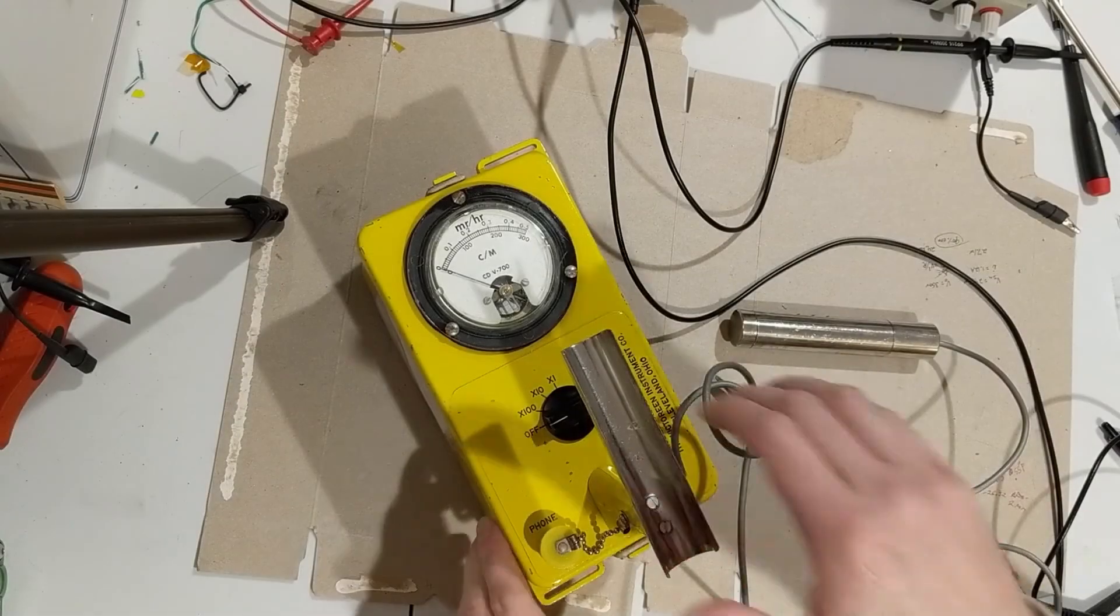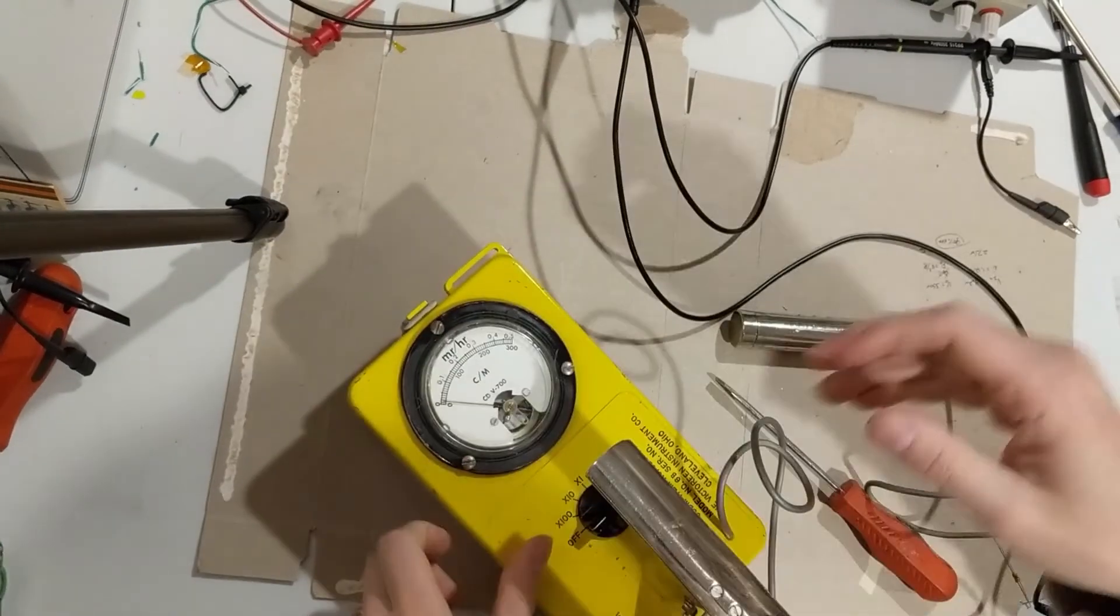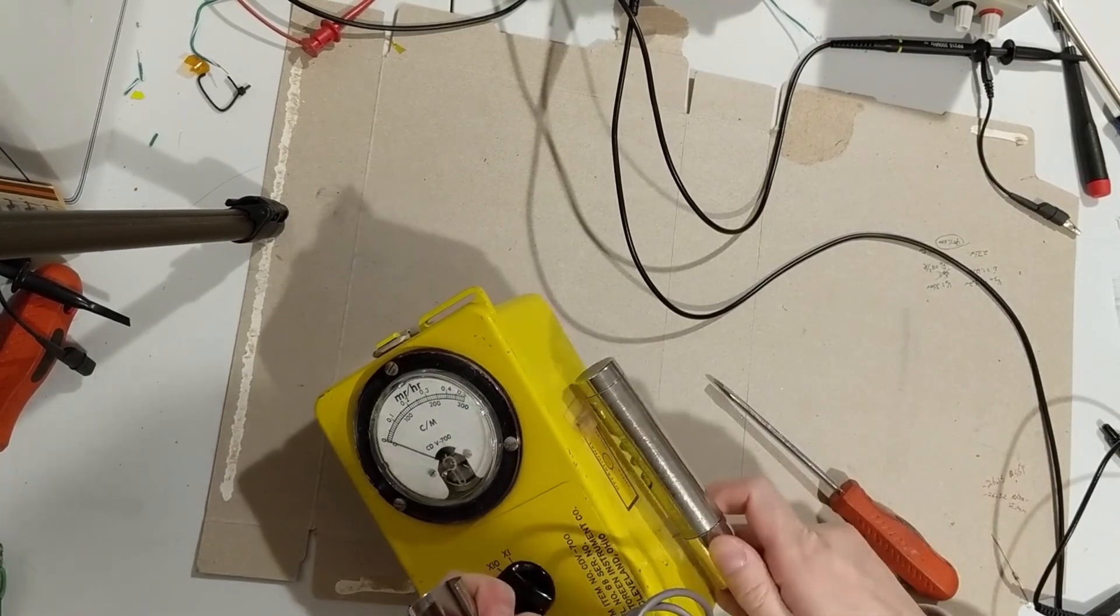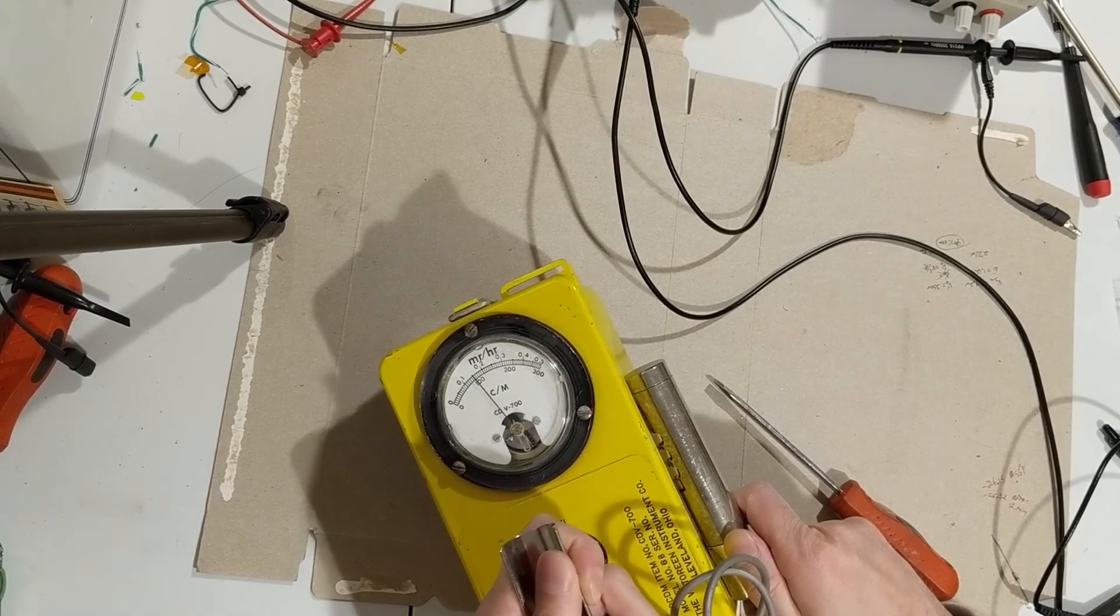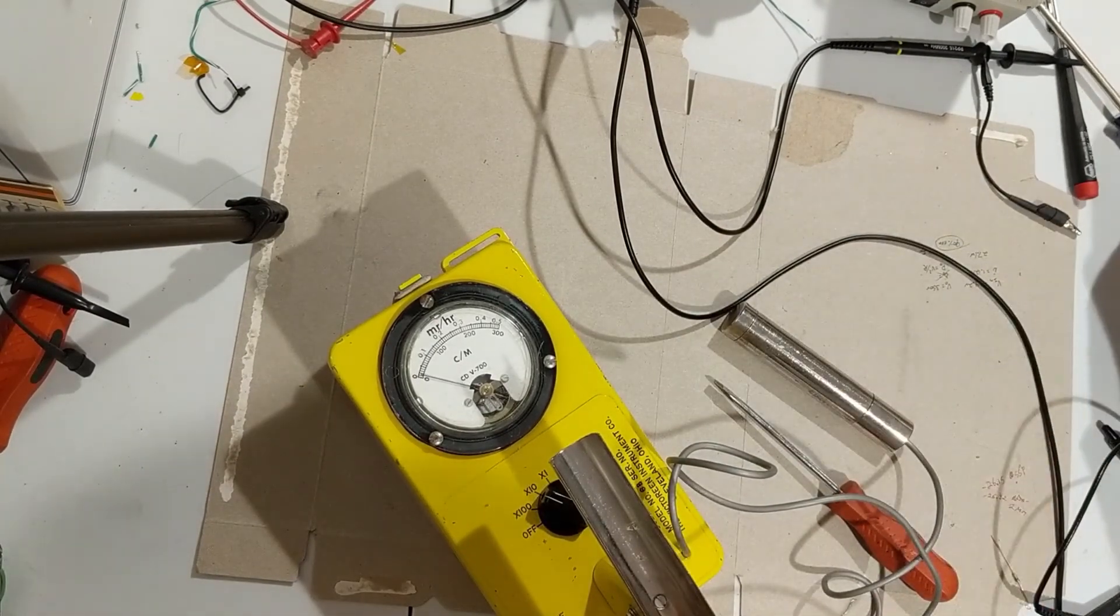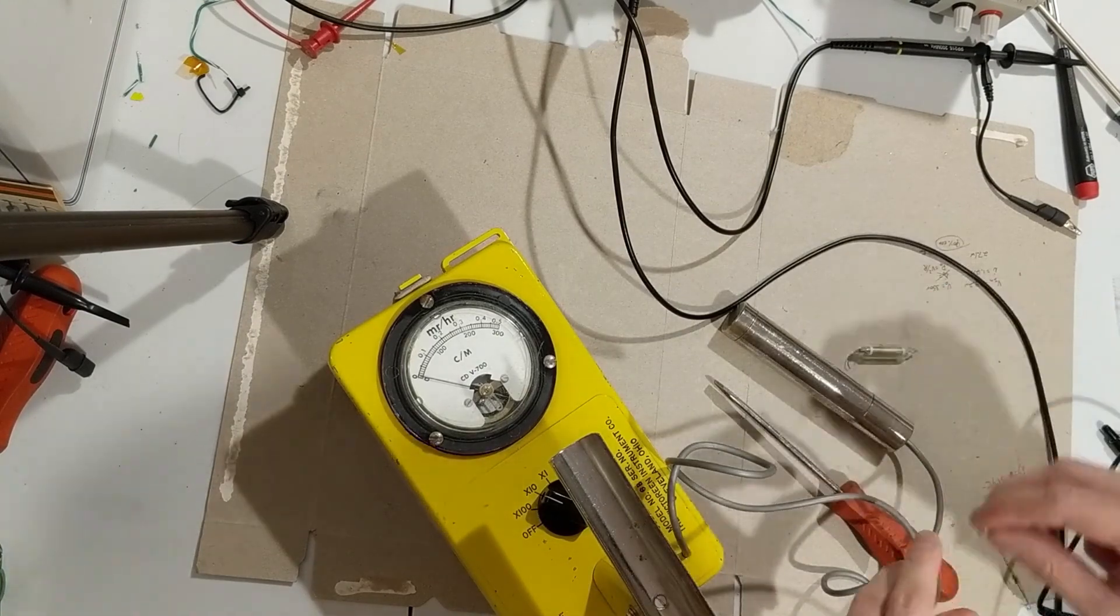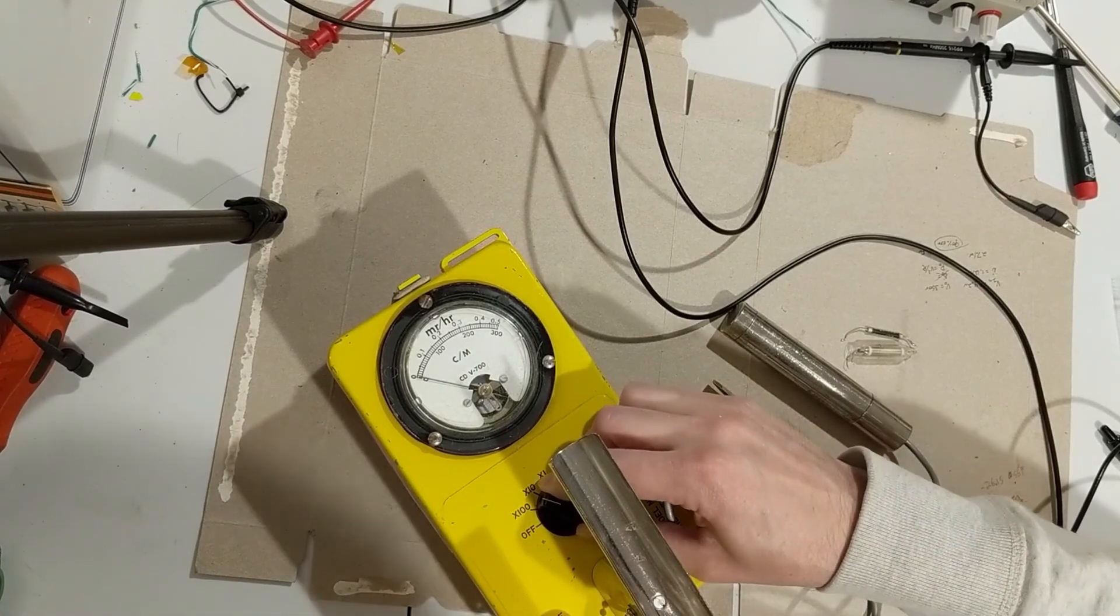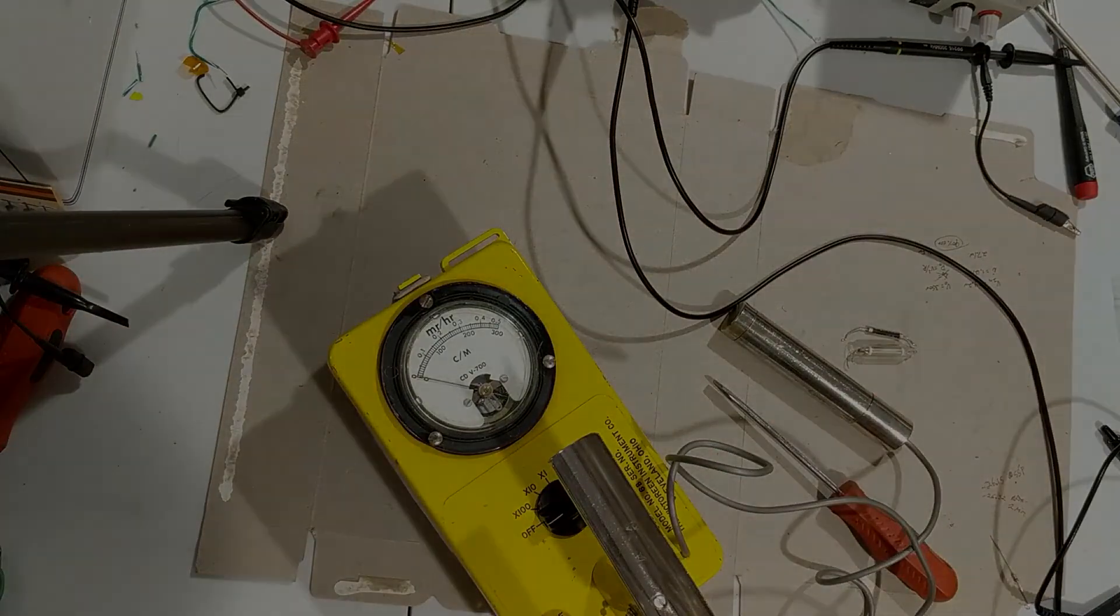So there we go, unit's back together. And we turn it on with this check source and I would expect it to be approximately 0.15 millirem per hour. So everything's good. It's pretty straightforward, the repairs. And it's as easy as just removing these two components and putting them back in. Hopefully this helps someone out. And if not, good luck. Thanks guys.